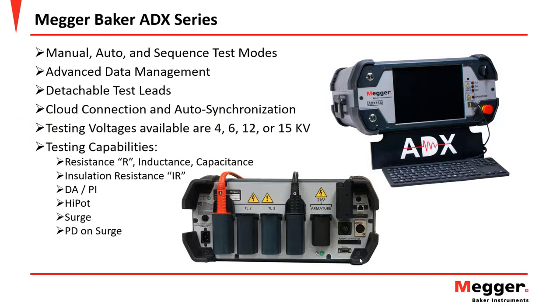There are a few things that are also new about the equipment. In the old days, we used to have leads that came out the front. Now they're actually detachable and they come out the back. Because there's high voltage in there, the leads themselves have to be protected. So there were grommets that would prevent the leads from being disconnected and connected. Since we've joined Megger, they've got some real expertise in this area of leads, and we're able to meet the standards of protection using detachable leads. So this is a real advancement, because we can then have different types of leads, different connectors, different lengths, etc. So a real nice added value there.